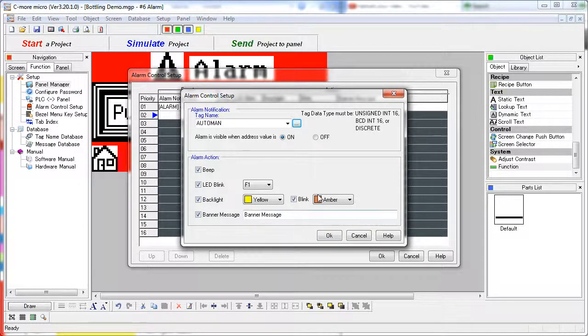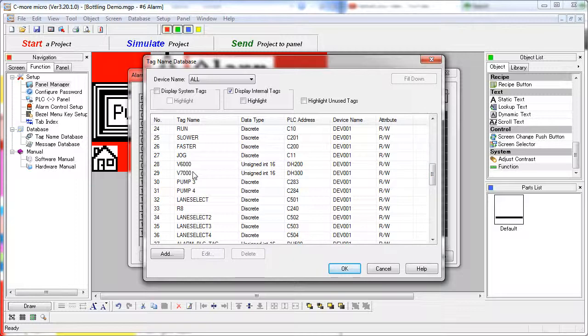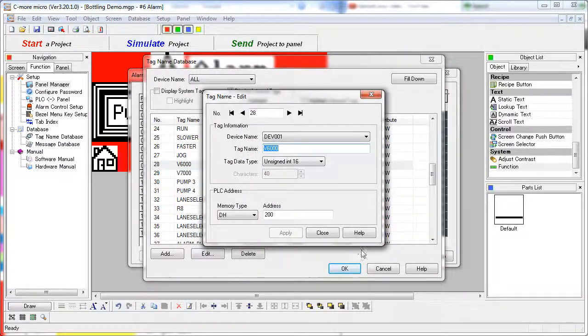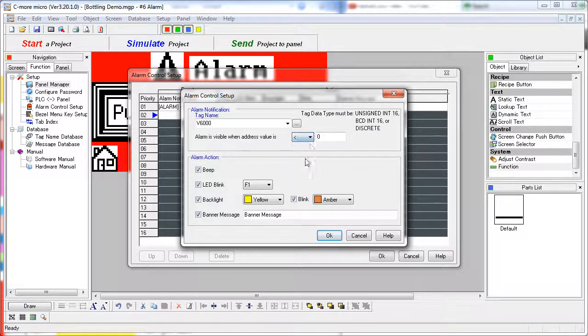One note: the alarm tag doesn't have to be a discrete type. If we choose a numeric type — for example this V6000 — notice that this changes from on/off to conditions. So the alarm is visible when it is equal to a value, not equal to, greater than, greater than or equal to, etc. You can choose any value and any condition you want for a numeric tag. Otherwise everything else is the same.